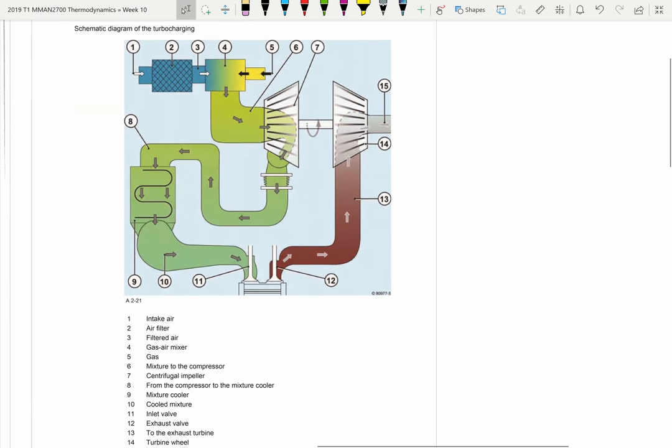What other information have I set aside here? Oh, yes. Cool. So this shows the air intake coming into the engine, going through an air filter, and then being mixed with the fuel gas. So 5 is fuel gas, 4 is a mixing chamber. Here's our turbocharger, number 7, and then it comes down to our intercooler, number 9. So this is where 60 kilowatts of energy are being removed from the airstream, and then it's coming into our combustion chamber.